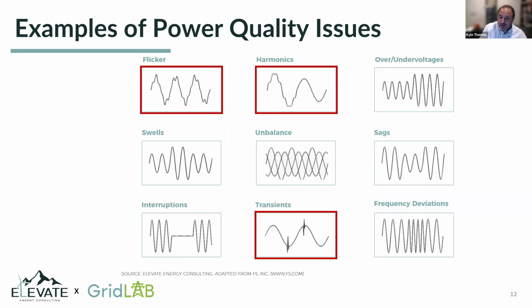Just as one example - we know power quality has been around for a long time. It was driven a lot by large loads of the past, like semiconductor manufacturing and other large loads. Same is true with data centers, and it's introducing flicker concerns, harmonic concerns, various types of transients, and almost any other ones you're looking at here. This type of load characteristic can cause all of these problems, and we're starting to see leading indicators that these are happening everywhere, in a sense. We need to resolve these, understand this, and share data to mitigate these problems - ideally in the interconnection process, not after the fact, after it's already operational.